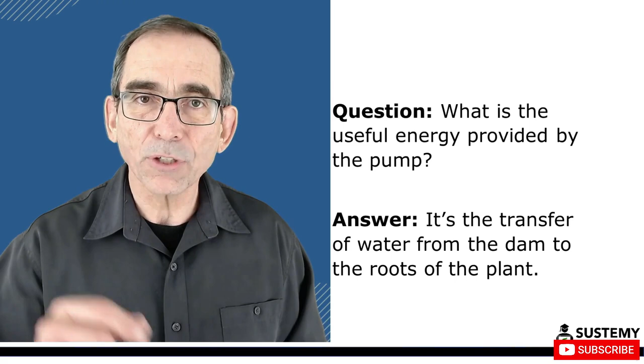We've got electricity into the pump, 100% into the pump motor. Then the pump motor itself, the shaft power is about 93% with 7% losses. Then let's say the pump efficiency is around about 65%. So of the shaft power into the pump, the useful efficiency going to pumping water is actually 65%, the rest is heat. Then let's say the water is then delivered to the roots. 40% of the water actually delivered to the plant goes to the roots, and then the rest of the water is lost, it evaporates or it goes on leaves, etc.